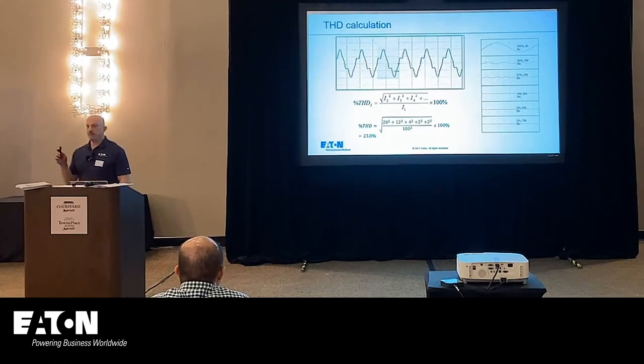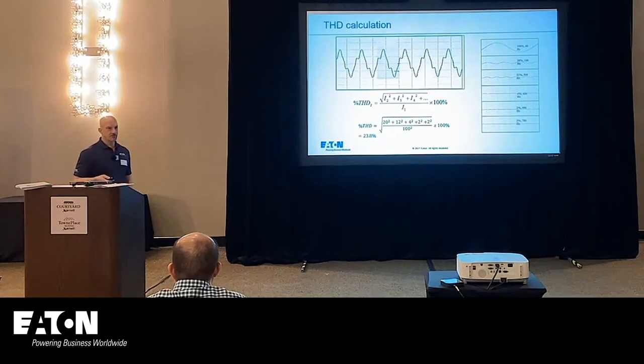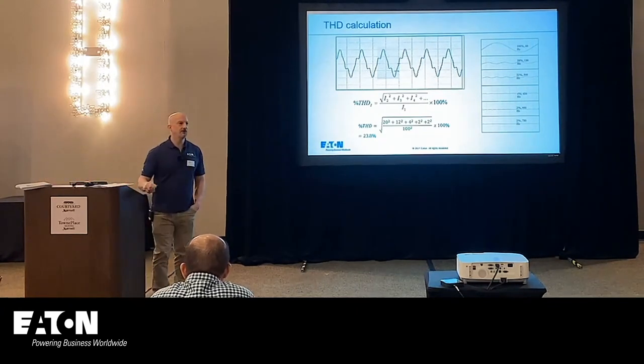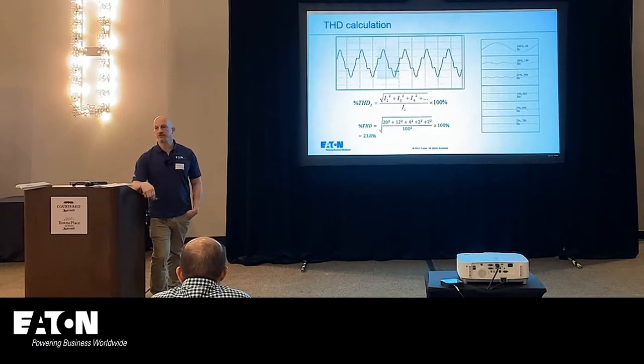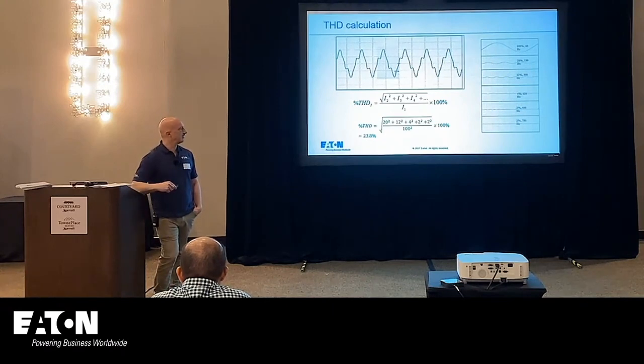But I want to tell you, be very careful when you're doing percent distortion, because what can happen is you can end up with a number like that, and then overnight you might drop your harmonics just a little bit, but let's say your 60 hertz increases a lot. Let's say you have a bunch of motors that are across the line. Let's say this number doubles.